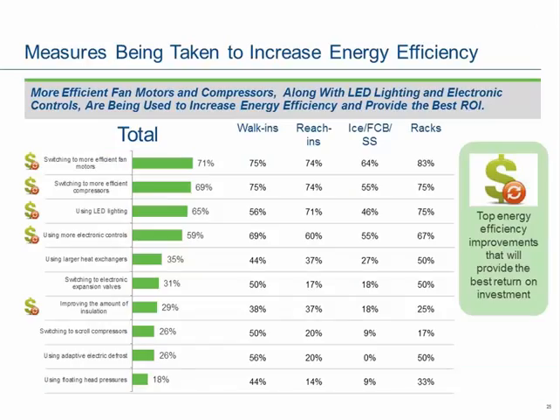This chart here shows the results of a survey that Emerson did to equipment manufacturers for all these equipment classes that we've been discussing today: walk-ins, reach-ins, ice, even the frozen carbonated beverage and soft serve, even though they don't have Department of Energy efficiency requirements right now. Equipment manufacturers are working to make that equipment more efficient. And this survey also included supermarket racks or parallel systems, larger parallel systems. And you could see all of these design options that we've been talking about, switching to more efficient fan motors and efficient compressors and lighting and controls.